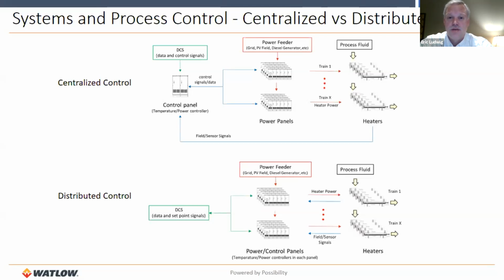So you basically have a multitude of power panels and a singular control panel. The DCS just talks to that control panel, and then the control panel could have any various types of controllers. It could have a PLC, could have a different type of temperature process controller in it. Those would then send the signals over to the power panels. The power panels would house those power switching devices we just talked about, either the contactors or the SCRs, and those would switch the power over to the heaters.